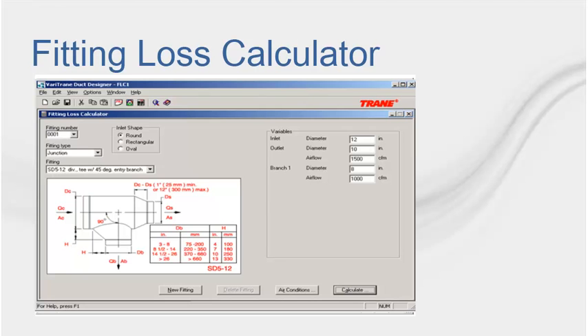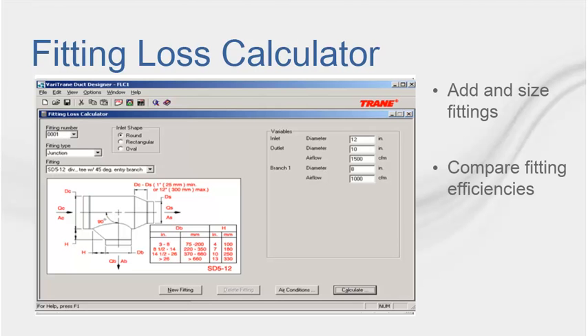There are two ways to use the Fitting Loss Calculator. The first is within Duct Configurator to add and size fittings within duct sections. In this case the applet opens a window labeled Fitting Input when you click on Add Inline in the sections worksheet. The second way is by itself to compare fitting efficiencies. To use the Fitting Loss Calculator this way, click on the Fitting Loss Calculator tab. Describe the fittings and applicable air conditions and the output will calculate the velocity and velocity pressure at the inlet and at the outlet, and the pressure drop and loss coefficient at each output.